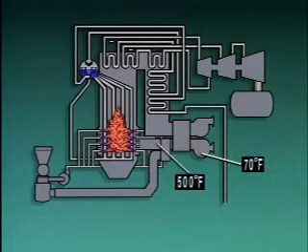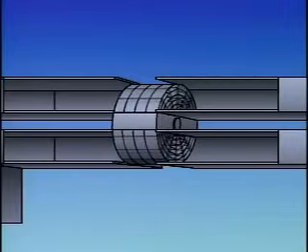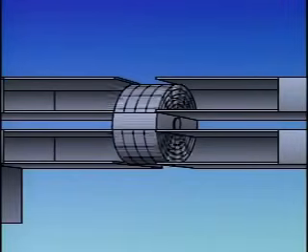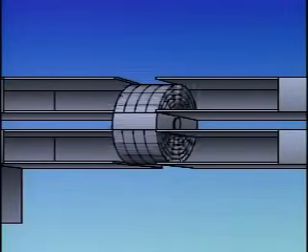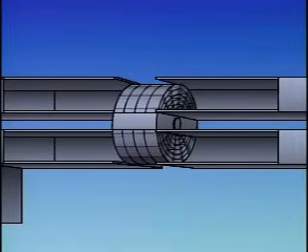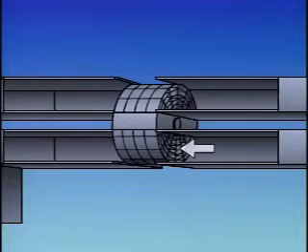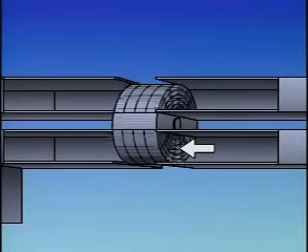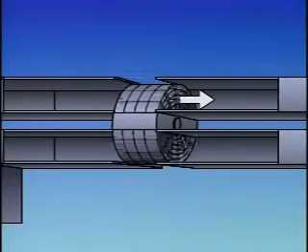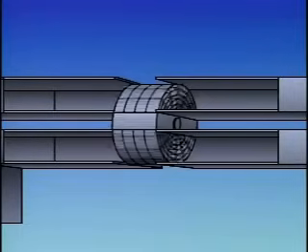There are two common types of air preheaters: rotary preheaters and tubular preheaters. In a rotary air preheater, heat transfer is accomplished by the use of a rotating metal drum. The drum contains a number of plates and is divided in half by a stationary seal. The seal helps keep the incoming air, which passes through one side of the drum, separate from the outgoing combustion gases, which pass through the other side of the drum.